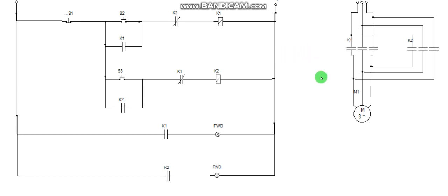we designed the panel to carry two different motors, right? So similarly, if you have such a situation in one enclosure, and it happens that one of the designs is forward and reverse operation and the other one is direct online, not forward and reverse. If you now revise this, during your distribution of the panel layout, you might decide to loop from contactor to contactor, from contactor to contactor, because you have two.